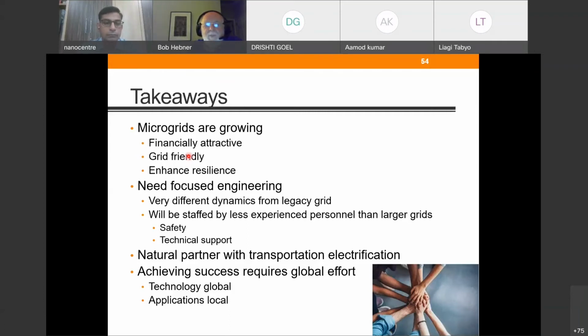The one thing we're going to need is focused engineering on microgrids, because they have very different dynamics from the legacy grid. As I pointed out, you need faster controls because you have lower inertia and loads that change more rapidly. In a major city, individual load changes may be very high, but the average load changes are very slow and predictable. As we get fewer and fewer clients on the system, the load changes become less predictable and faster, and so we're going to have to do a different type of engineering.